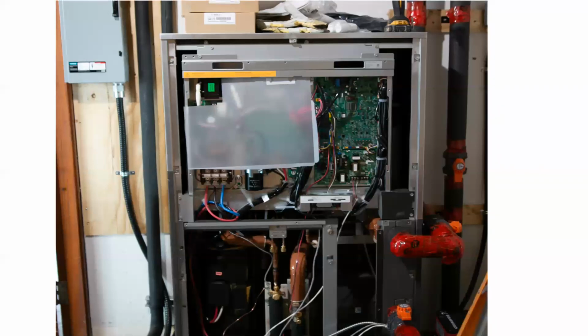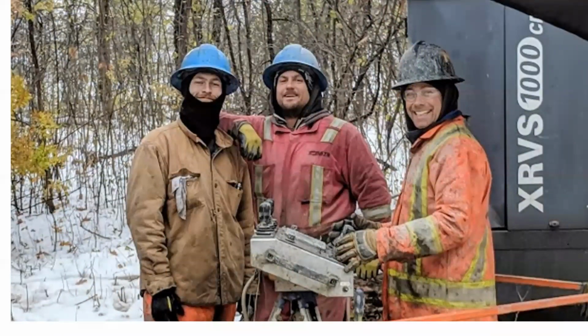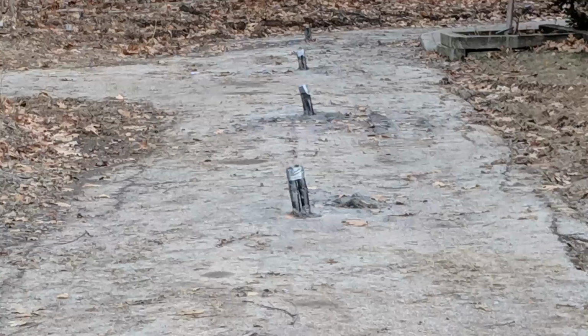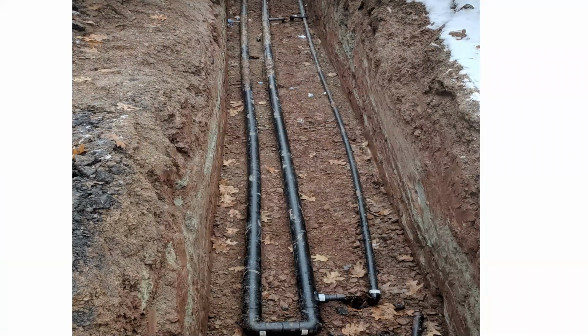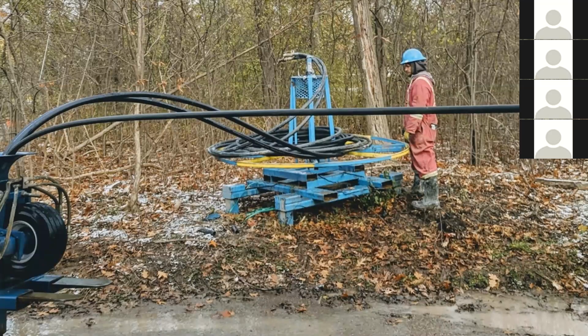One issue we ran into was communications, because we set up with Mitsubishi for the heat pumps and fan coil units, and with Grundfos for the water circulation system. The two units are supposed to be able to talk to each other, but we found it difficult to get the two companies to relate to each other. So that's an important factor when looking at these things — try to pick equipment that can work together between the heat pumps and the water circulation systems, because it will save a fair bit of money in the long term.